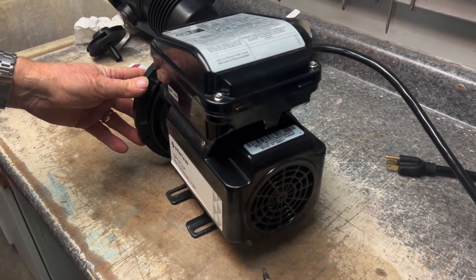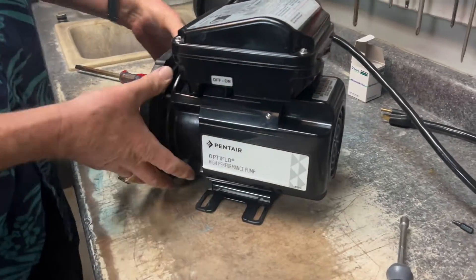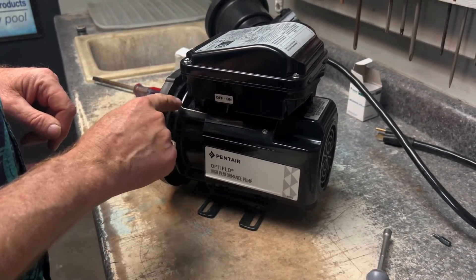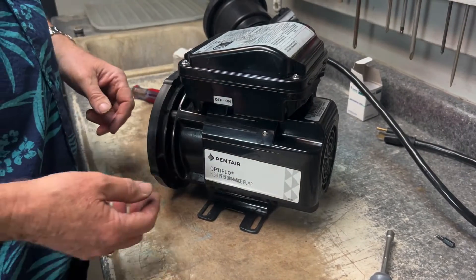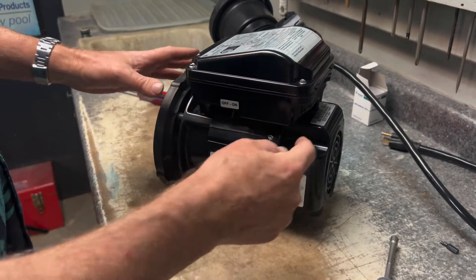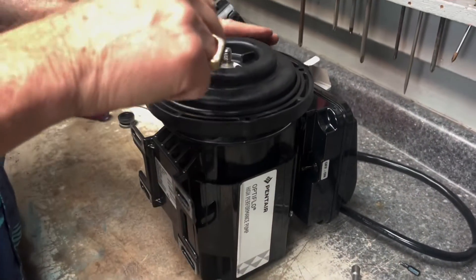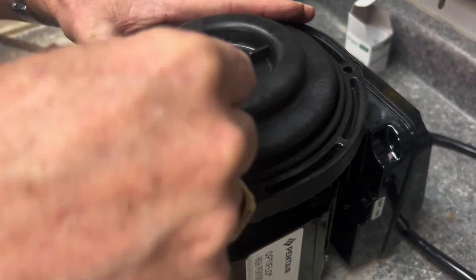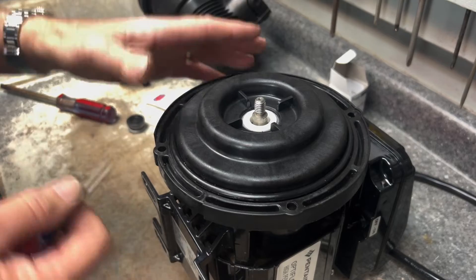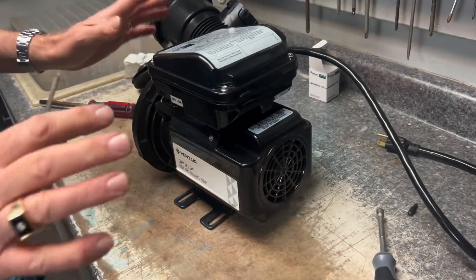Now we've got the seal plate on and we're going to tighten it nice and snug. Very important to note: if when loosening the seal plate a bolt is hard to turn, be careful — sometimes a bolt can rust inside the grommet on the seal plate. If we break that bolt it's stuck inside and we'd have to replace the seal plate. In that case you can take a flathead screwdriver and pry between the rubber and ceramic part to get it out. Just be careful not to damage the seal plate — the old seal is being replaced anyway.